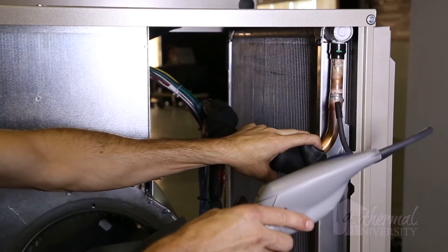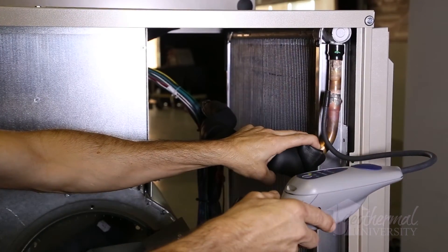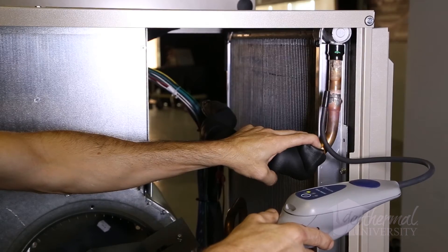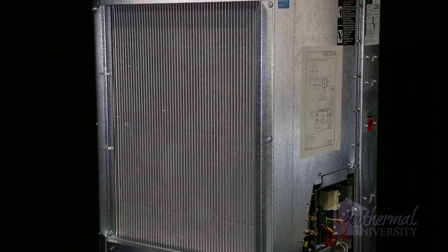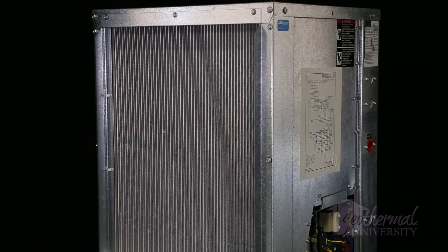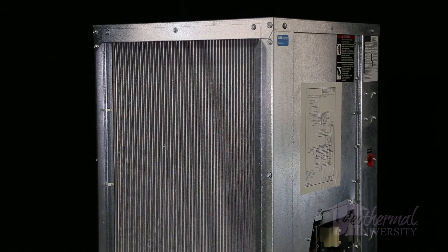If you have followed along and not found the source of the leak, we'll need to examine the evaporator coil more thoroughly. In order to avoid time consuming labor to strip off covers, ducting, blower cages, or removing the components, an easy electronic screening method is recommended.